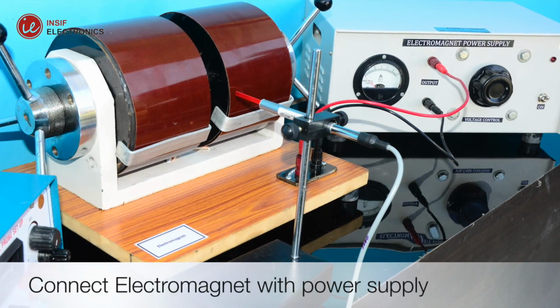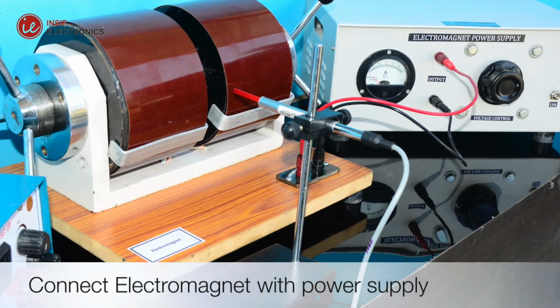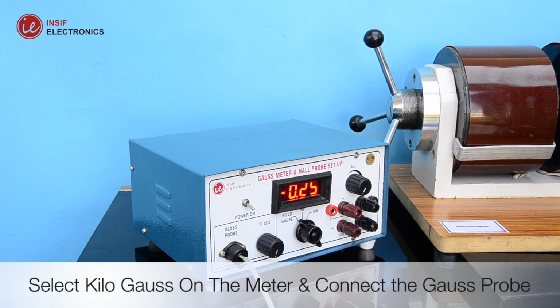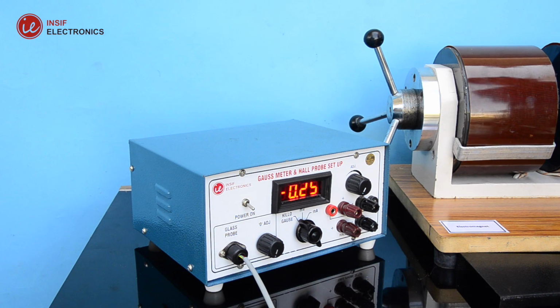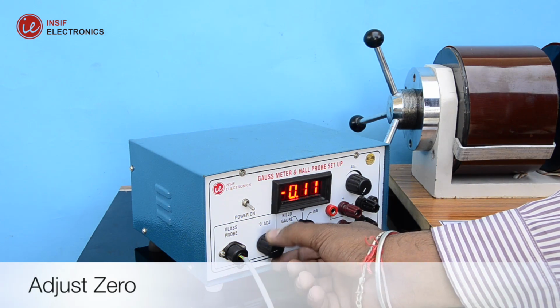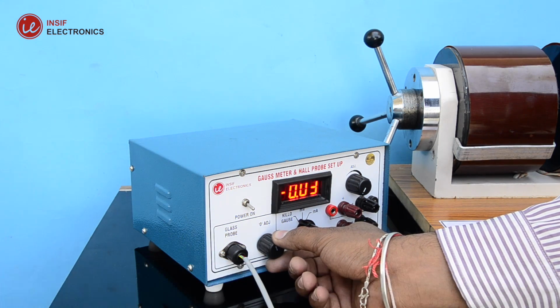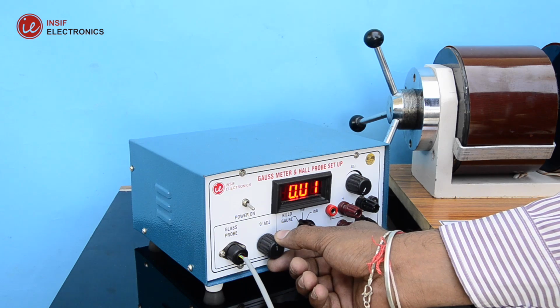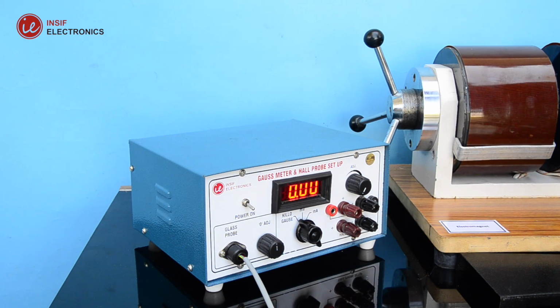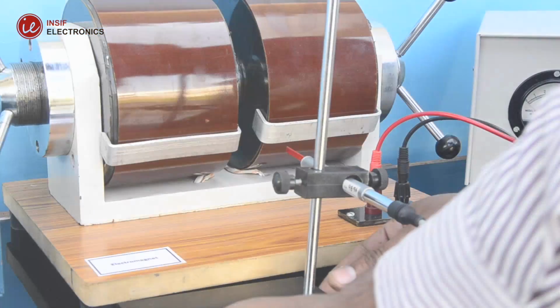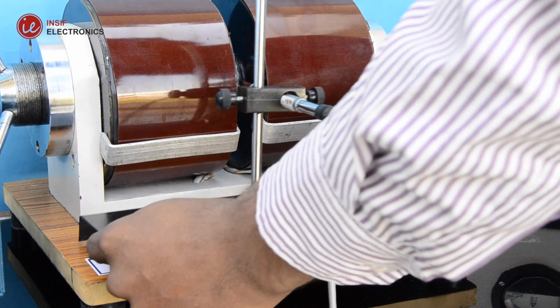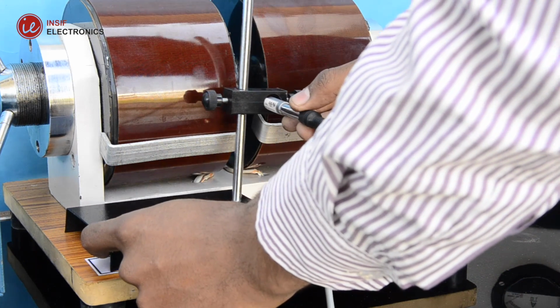Firstly, connect the electromagnet to the power supply. Now select kilo Gauss on the meter and connect the Gauss probe. Now adjust zero by rotating the knob, so that the display will show zero. While adjusting the zero, make sure the Gauss probe is not placed between the magnet. Then place it carefully at the center of the electromagnet.